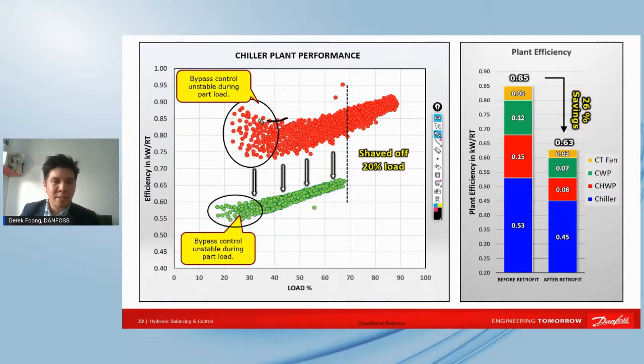And this is why you see in the curve that these red colored dots are before retrofitting the system, and you can see there's a wide maximum deviation right here. And even at less than 30% load, we were relatively stable. You can see that the lower the load, the more savings we get and the more efficient the system is, for magnetic levitation compressors. So when you have VSD in the compressors of the chillers, it operates better during part load.